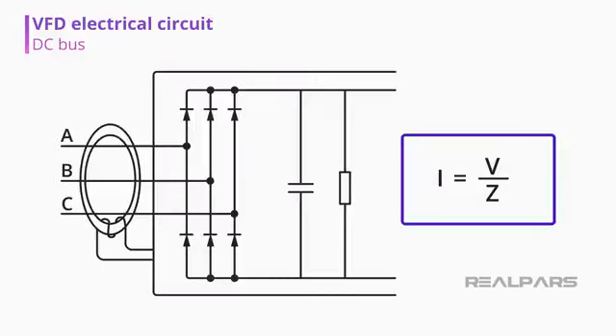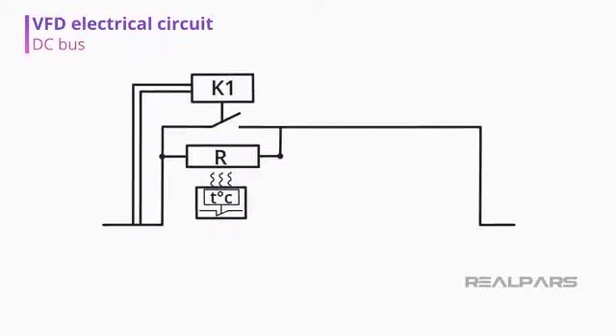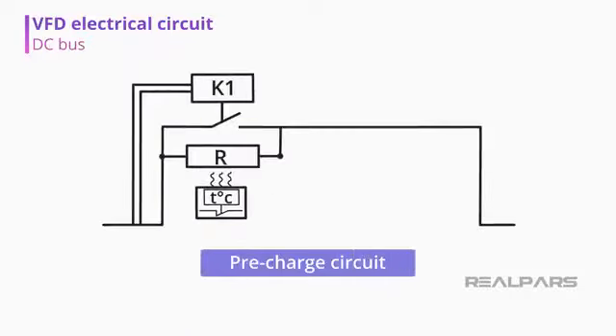Since the capacitors are not charged, their impedance is very low. If we were to charge them, the initial inrush could damage the input power devices, or the rectifier converter, in case the entry fuses didn't interrupt the circuit. So instead, we have a pre-charge circuit.